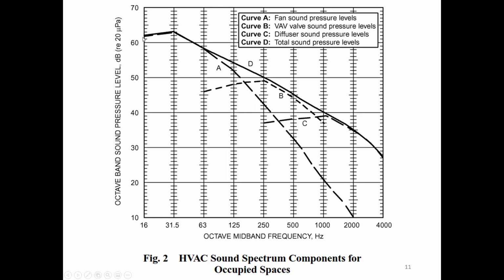So first let's talk about what it makes up. You have A, which is the fan noise—that's more the lower frequency rumbly stuff. And then B, so VAV, that's variable air volume. A lot of times you'll have one big air handling unit that supplies the entire building, and then these variable air volume units are kind of like dampers that are controlled.